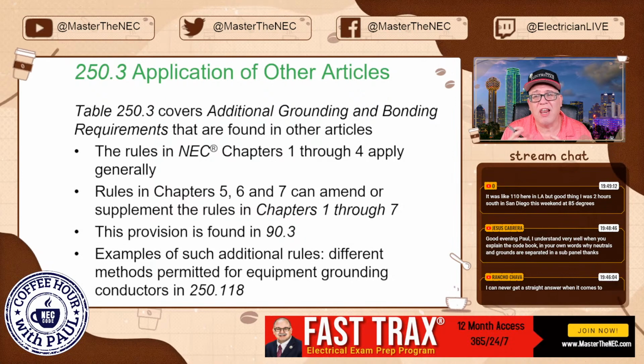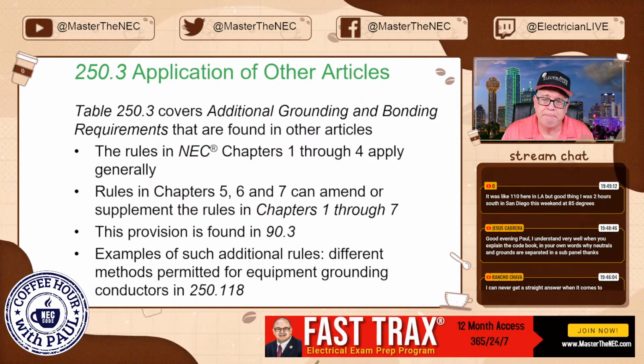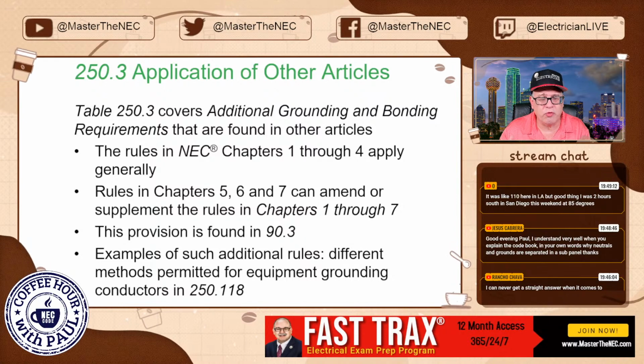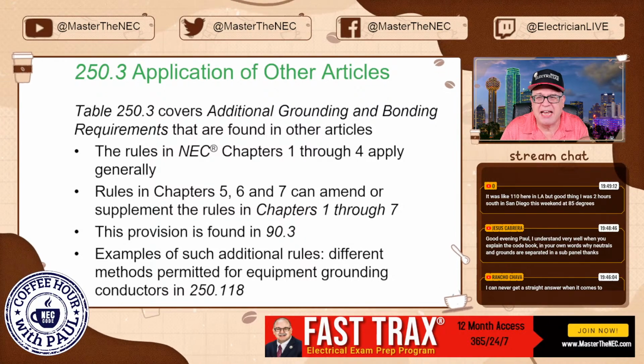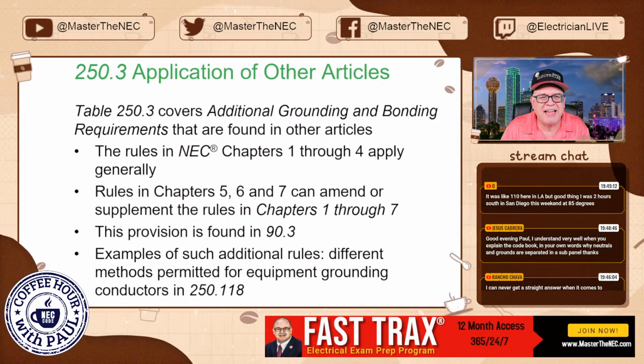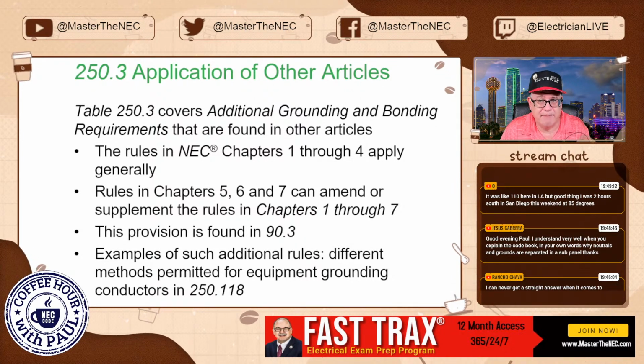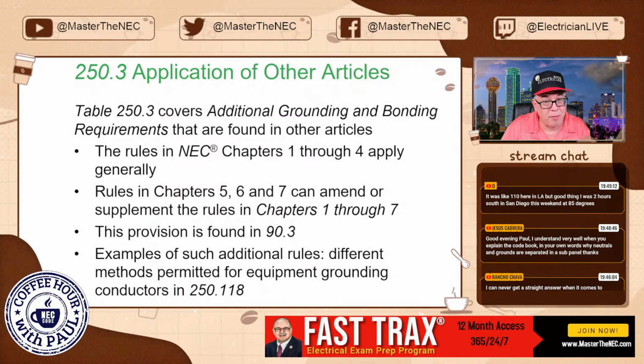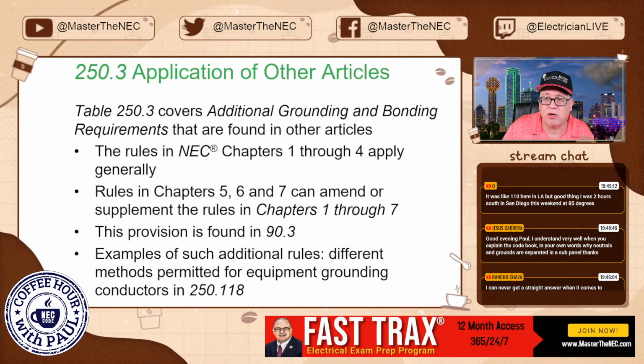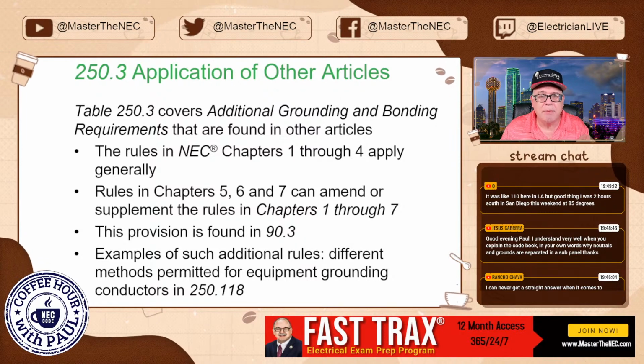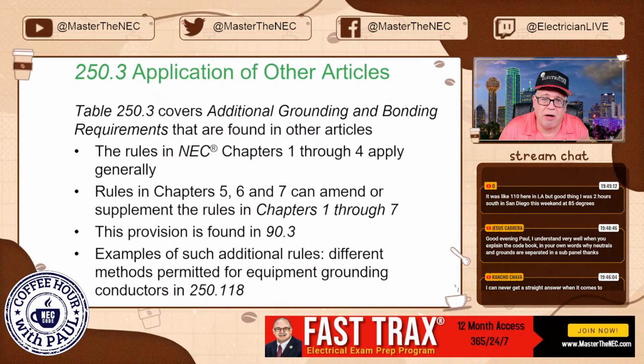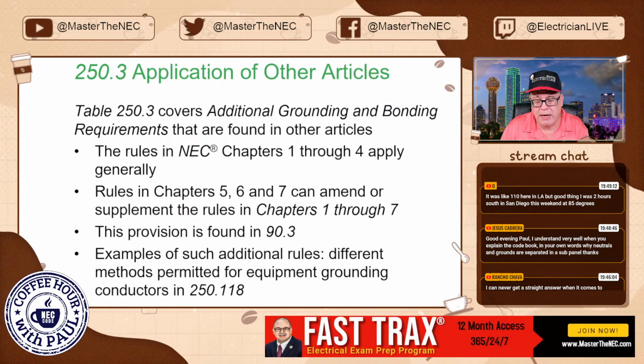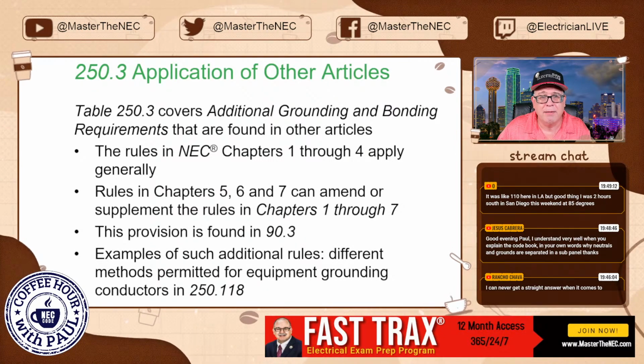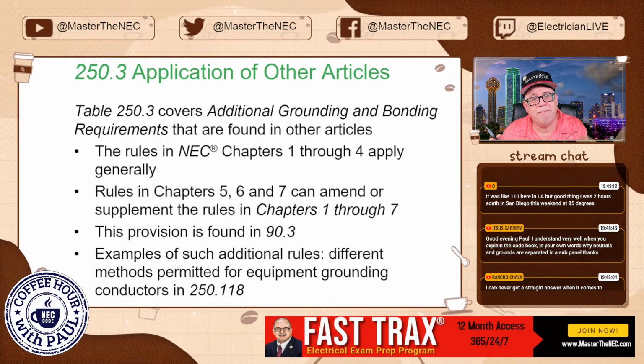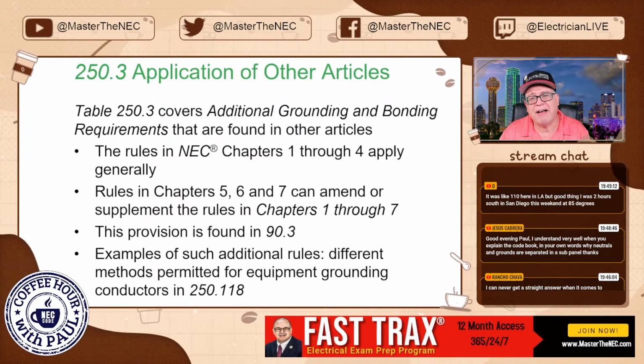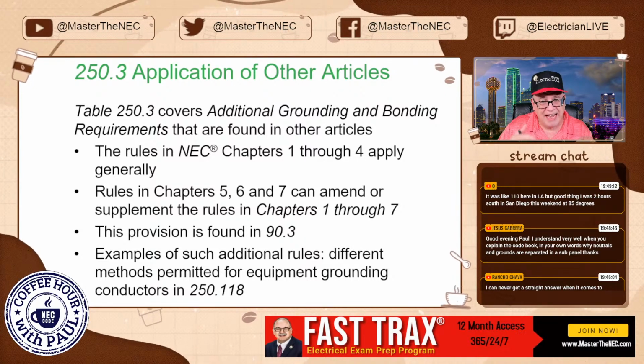So we do a lot with grounding and bonding in Article 250, but you remember there are rules that we have, let's say in 517.13(A) and (B) for a healthcare facility. That's got its own rules about redundancy, and it talks about having the armor or the raceway itself qualifying as an equipment ground if you're in a patient care space. But then you also have an insulated equipment ground. Now, Chapter 2 says equipment grounds can be what? Bare, covered, or insulated. But you have a specific requirement that is modifying it in 517.13(A) and (B). And so that's a great example.